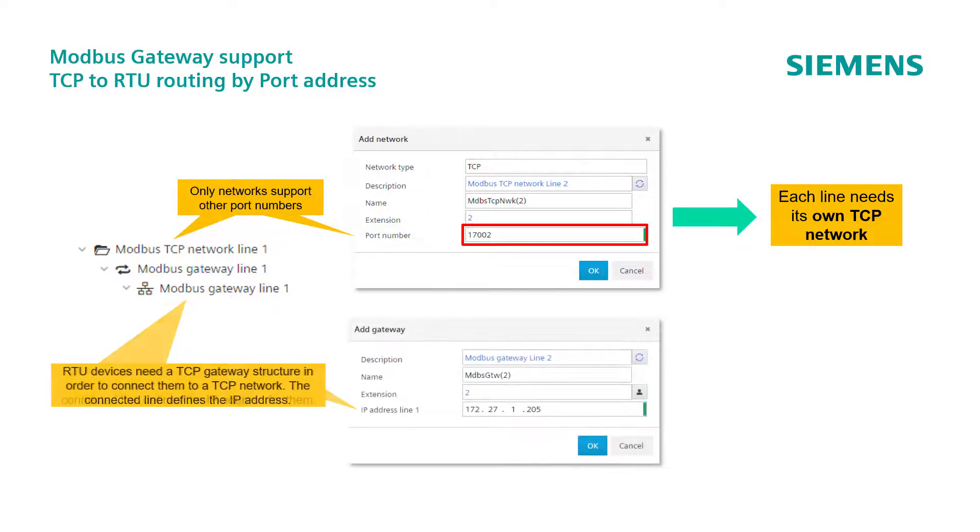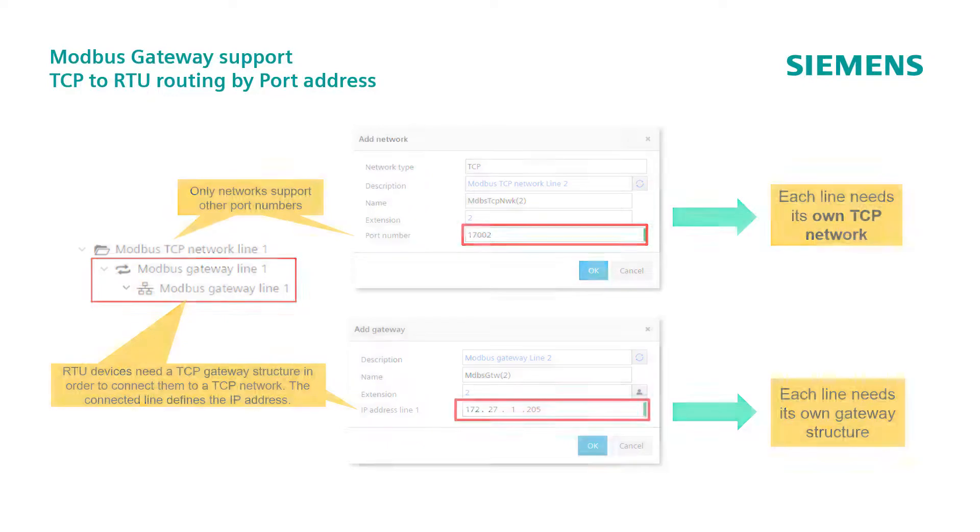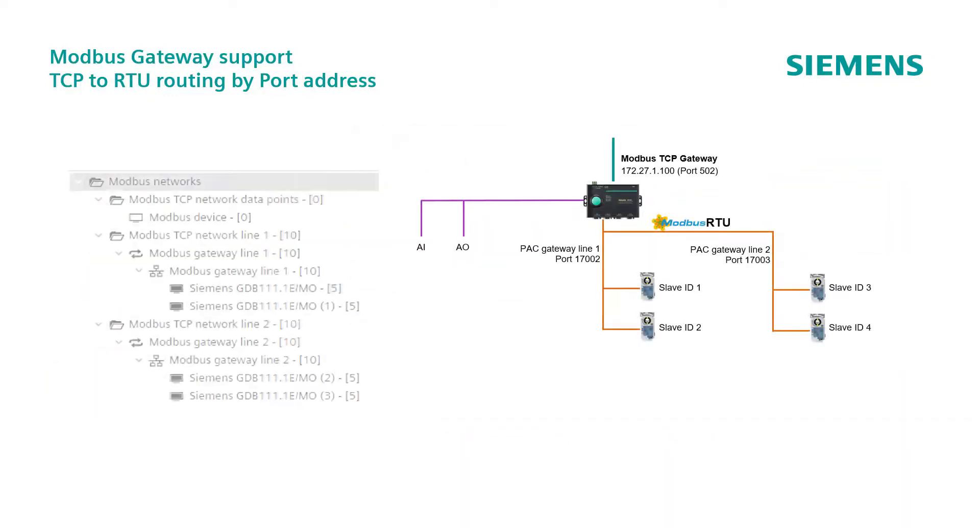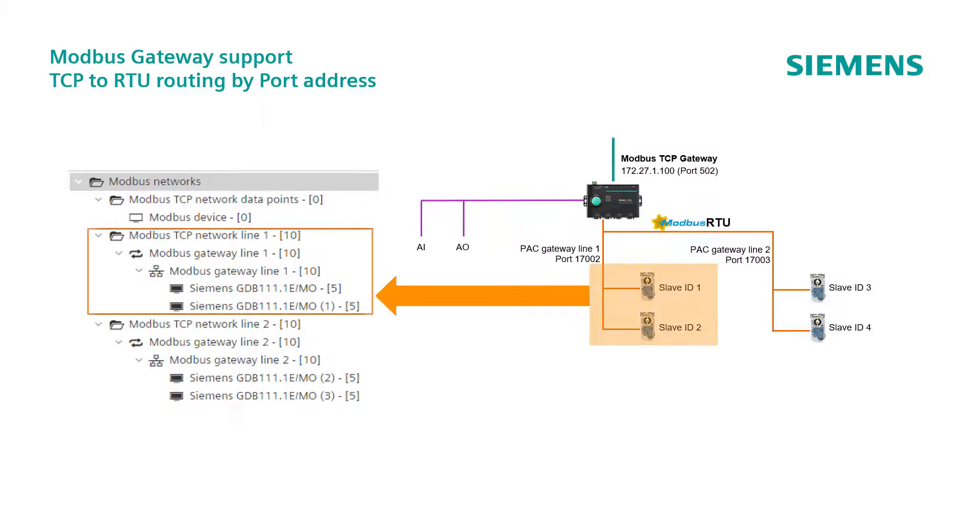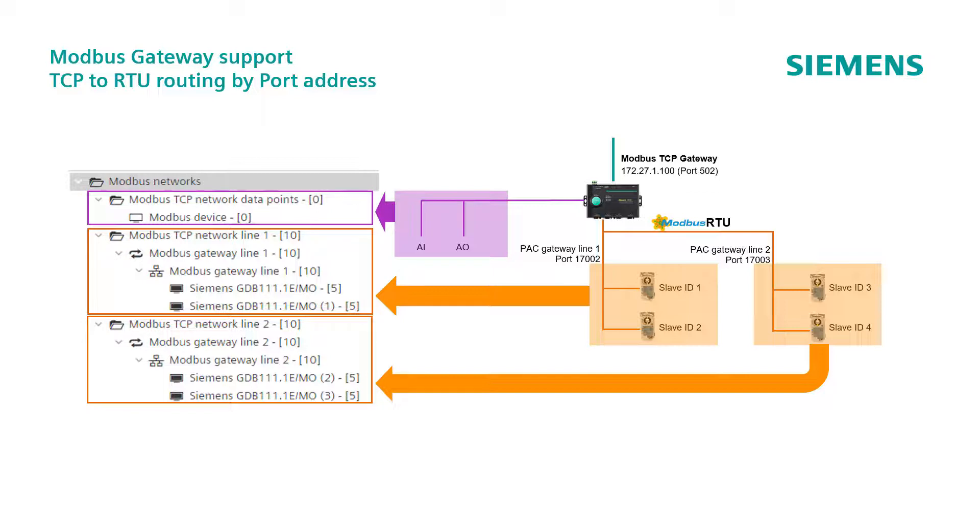At the same time, the IP address of the gateway itself, is supported by the gateway line node. So, each line needs its own gateway structure. As consequence, every single line will be comprised of its own TCP network line, its own Modbus gateway, that in the reality is always the same, and the line itself. Additional data points connected directly to the gateway, will have their own network, as we have seen in the first example.